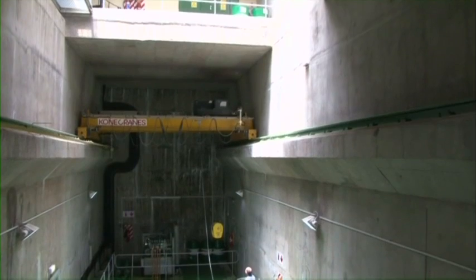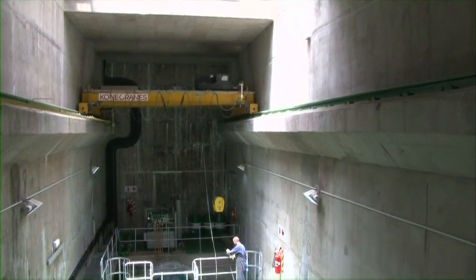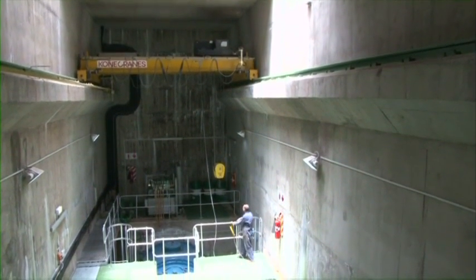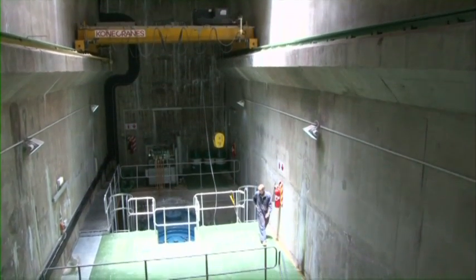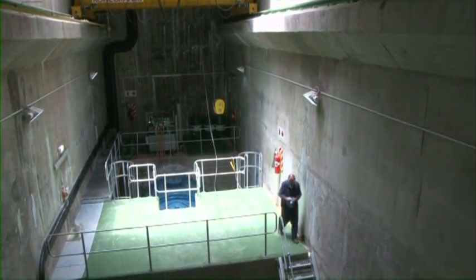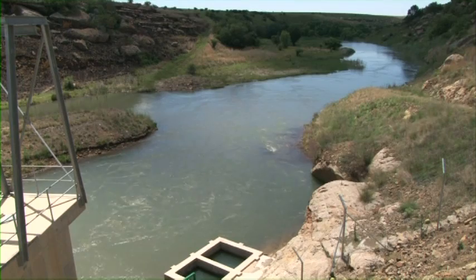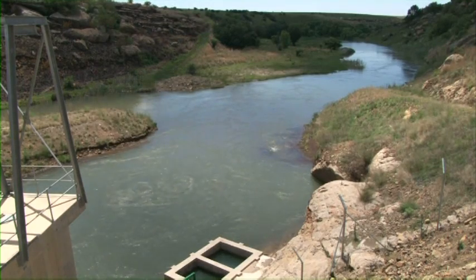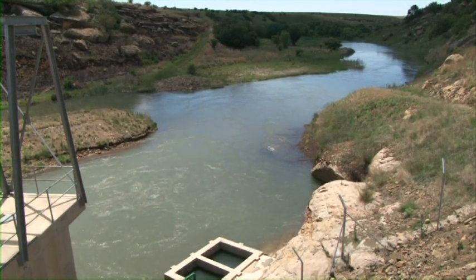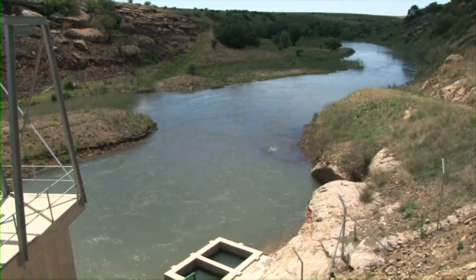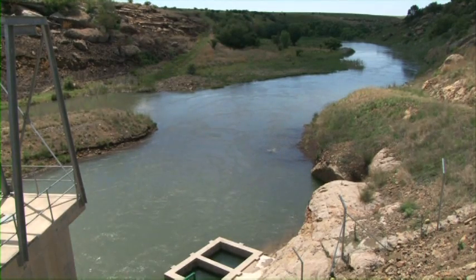Low-head power station with Kaplan installations, the excavations are quite deep because you need what they call a pressure difference behind the runner blades. So the turbine must be, in our case, 5 meters below the tail water race level. The tail race level is the level at which we put water back into the river. That avoids cavitation. Cavitation is the process at which a differential in pressure at the front and the back of the turbine blades causes the turbine blades to cavitate or erode.